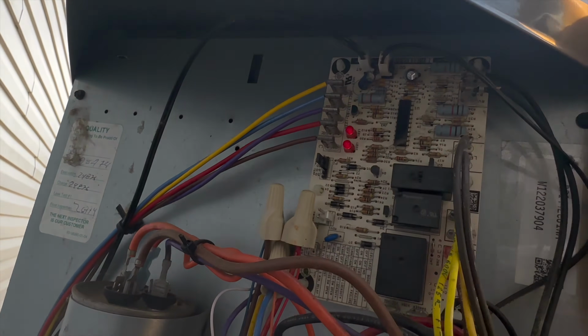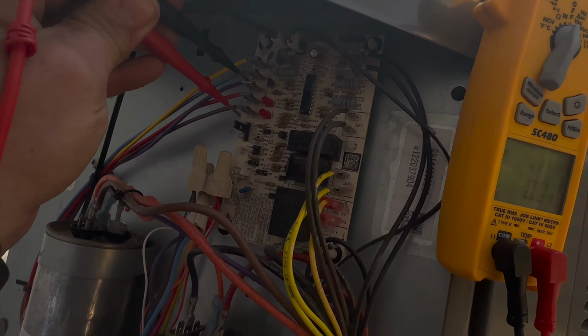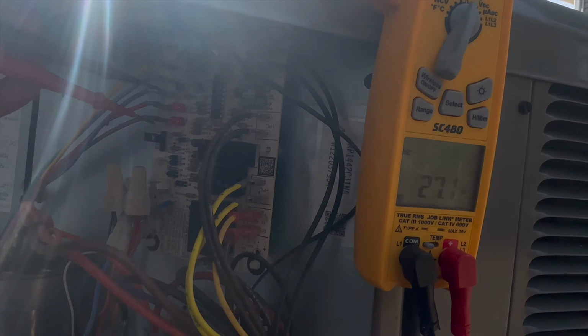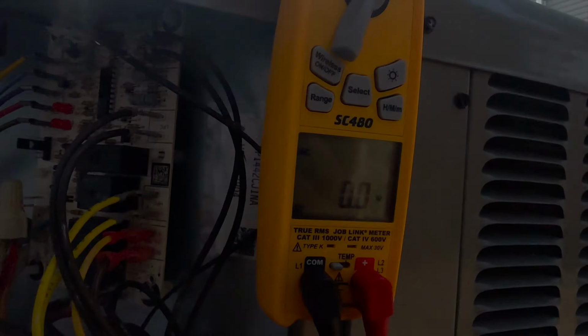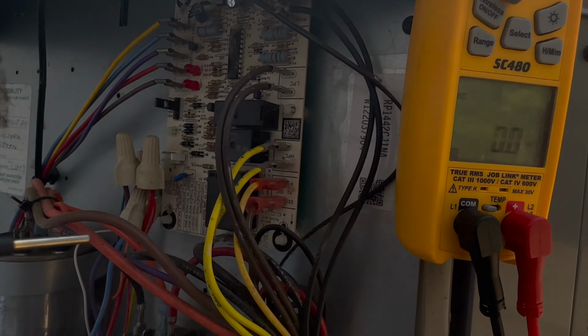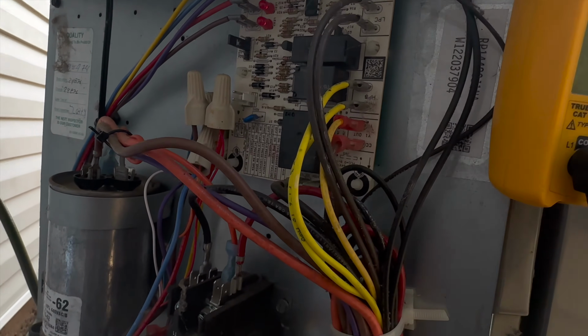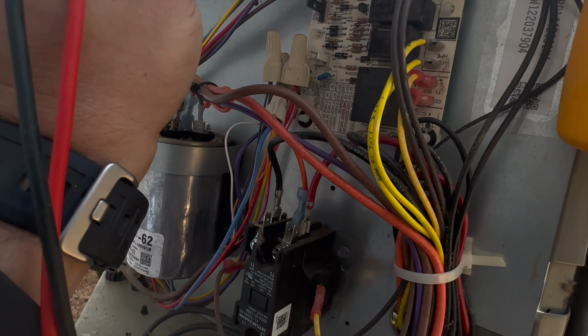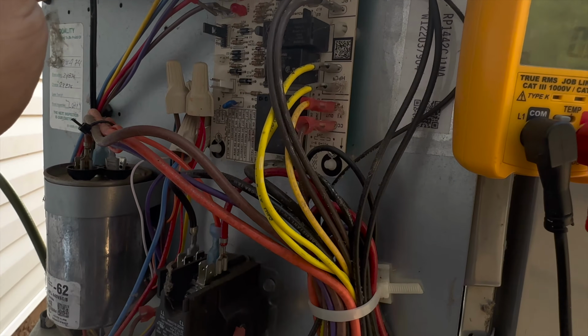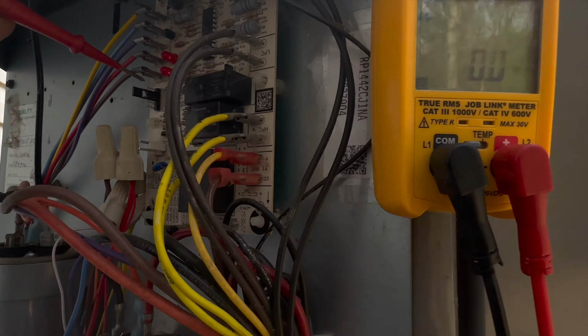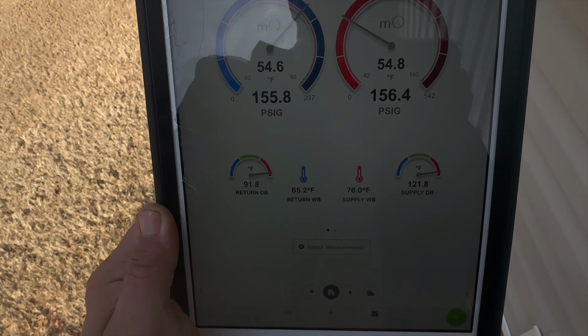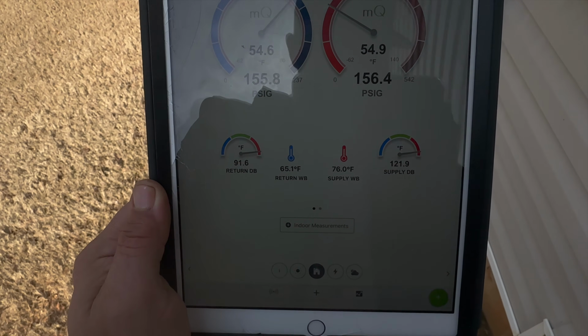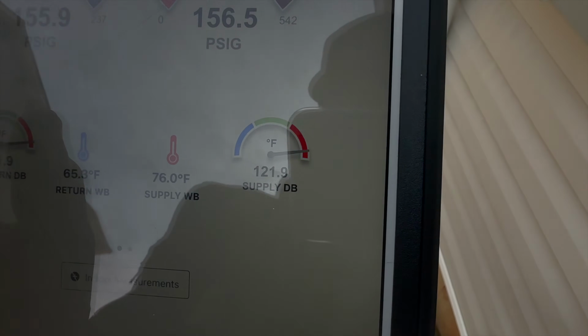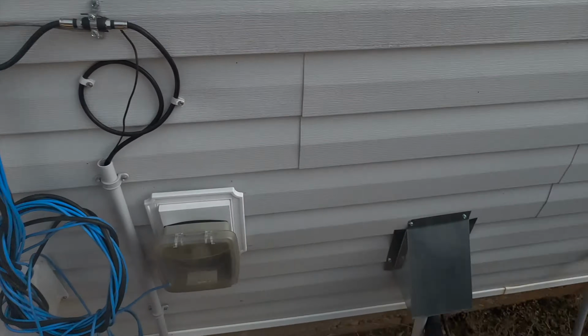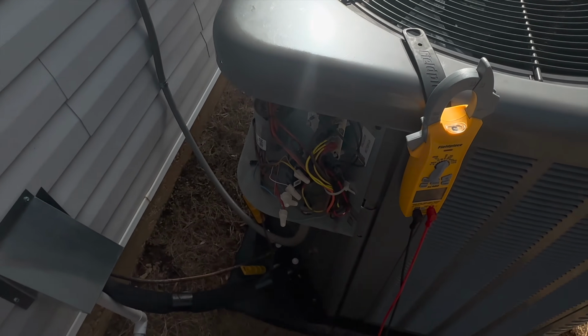Well, first thing I'm going to check is C to R, and we are getting 24 volts there. Now we'll check C to Y. C to Y is going to let us know if it is getting power, saying that this contactor should be pulling in. No voltage. Heat strip is definitely working. We are getting 121 degrees for the supply. So we know that heat strip is the only thing that could be heating this thing right now.